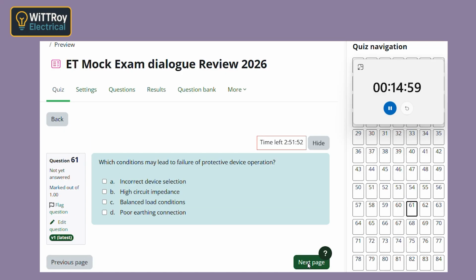Correct. Question 61. Which conditions may lead to failure of protective device operation? High circuit impedance and poor earthing? Yes, and also incorrect device selection. Let's link those properly. If circuit impedance is too high, fault current may be too low to trip the device quickly. So the fault is there, but not enough current flows to force disconnection.